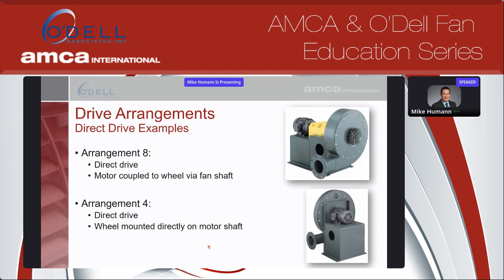Some of the benefits of arrangement 8s are, you can handle higher temperatures with these arrangements. You can handle corrosives because you have that motor away from the airstream. You can put a better shaft seal on there as well.